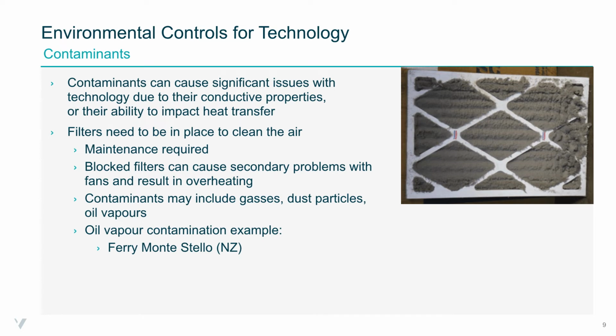Now, that reduction in airflow in itself can cause an issue because we have less cooling effect. It also causes downstream issues with the circulating fans that are providing that positive pressure to cool the downstream equipment. So we have fans labouring against essentially a blockage in an airflow column. We have, as you can see there, contaminants that are possibly making their way past the filter because it's exceeded its useful lifespan and function.